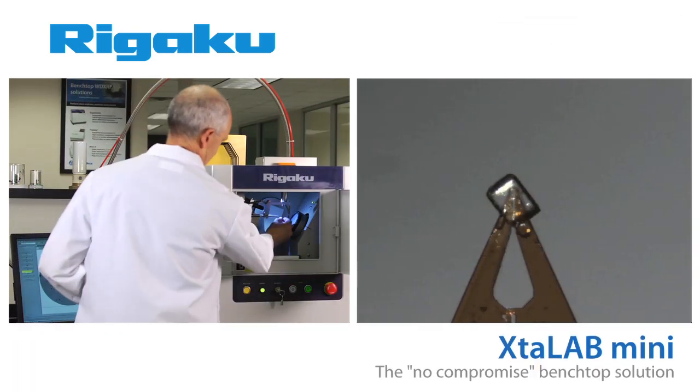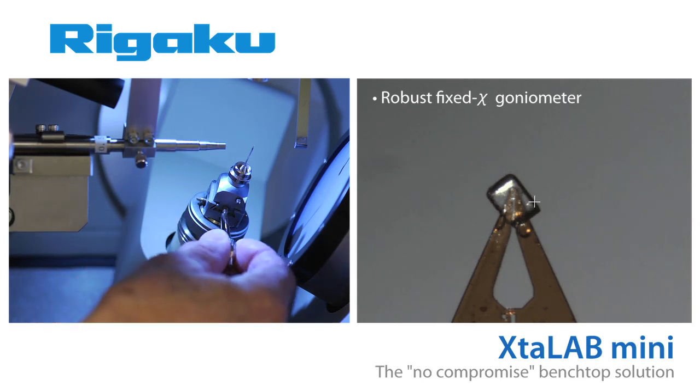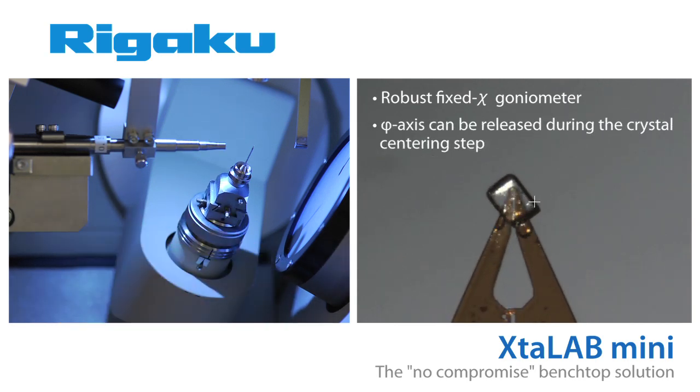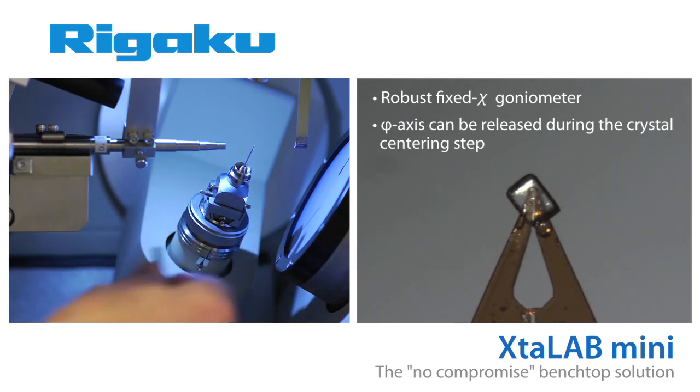Combined with this green x-ray source is a robust fixed chi goniometer, the heart of the XtaLAB mini. The phi axis can be released during the crystal centering step, making this critical task much easier to perform.